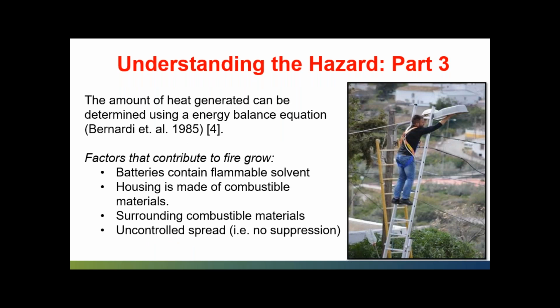So for the amount of heat generated, going back to engineering classes, we can use the energy balance equation. That's important for manufacturers, but also important if you're storing a tremendous number of batteries, such as at a recycling facility. You can use that information to make sure your fire suppression or response system has enough capacity to deal with that amount of heat.